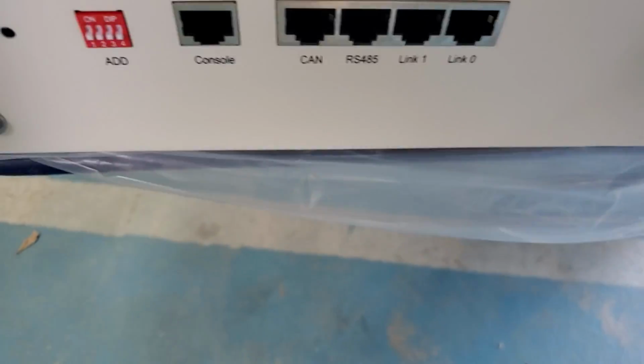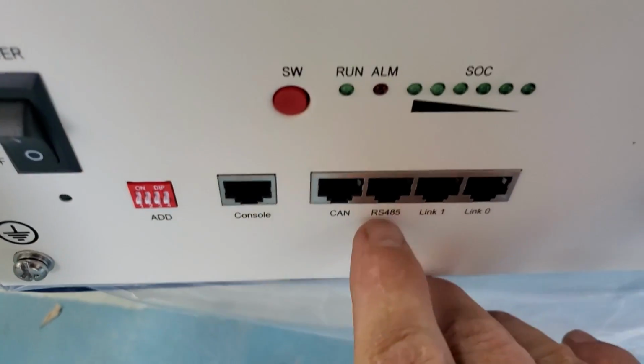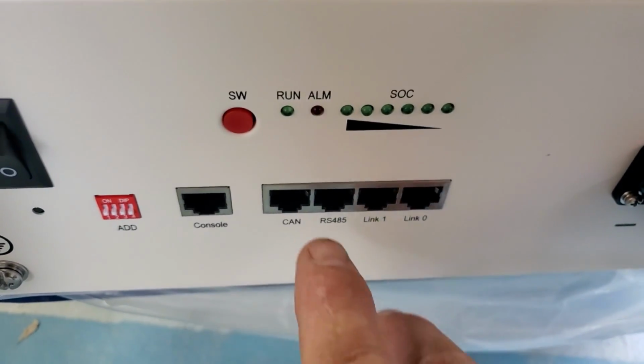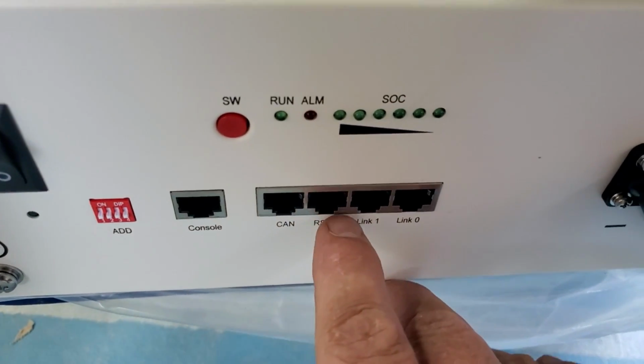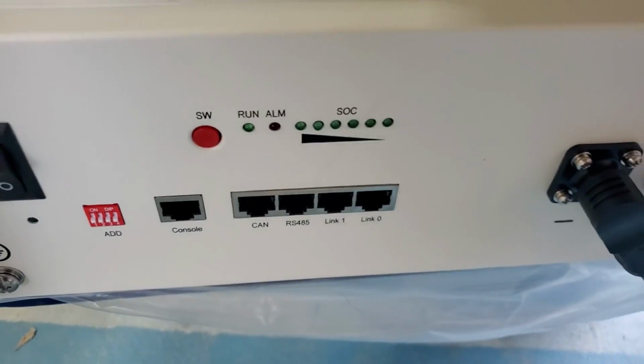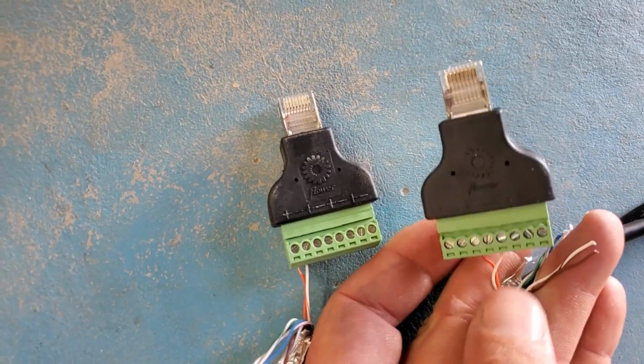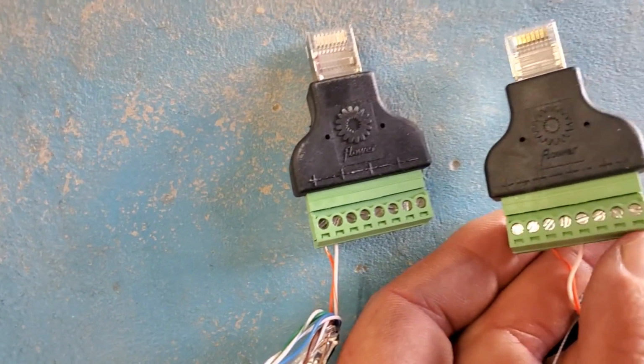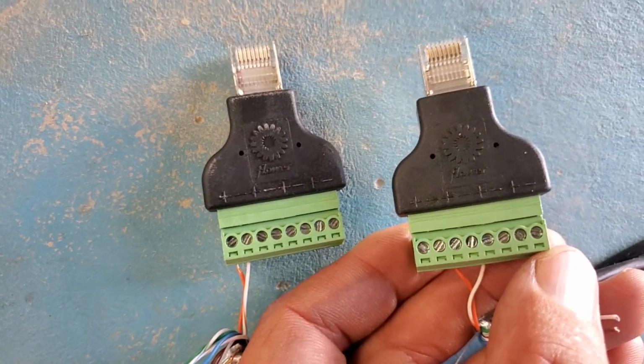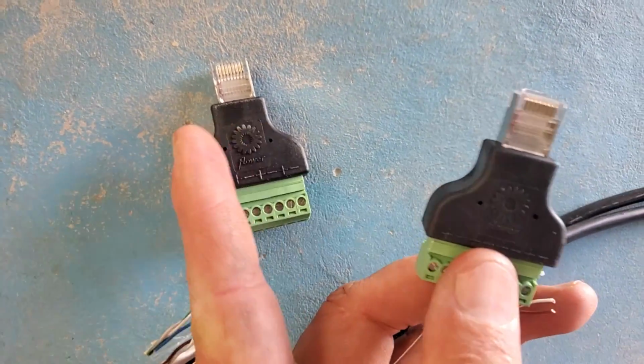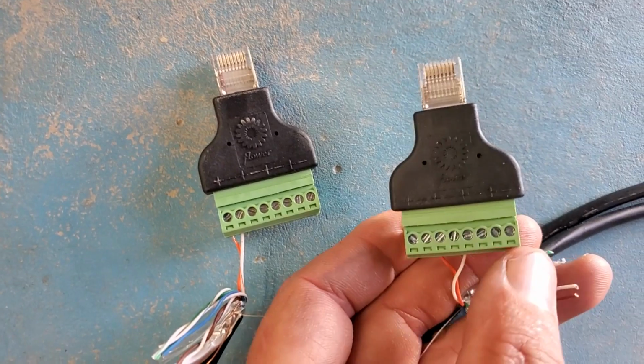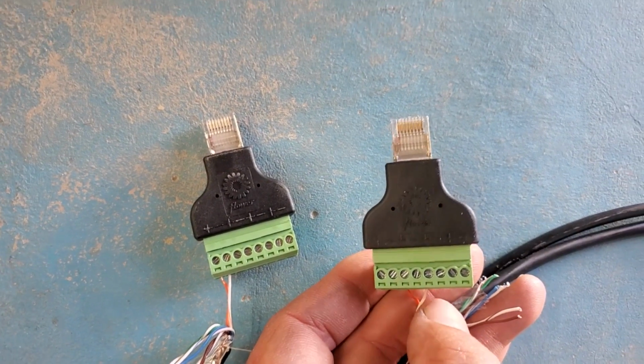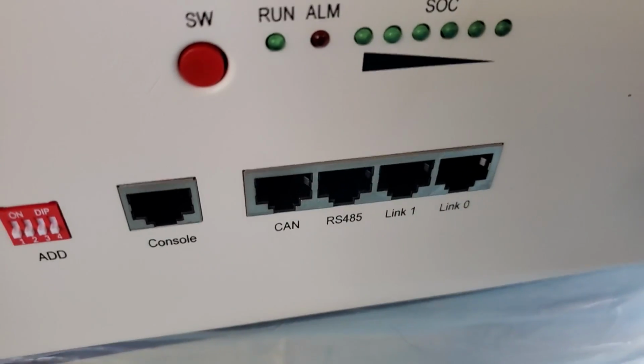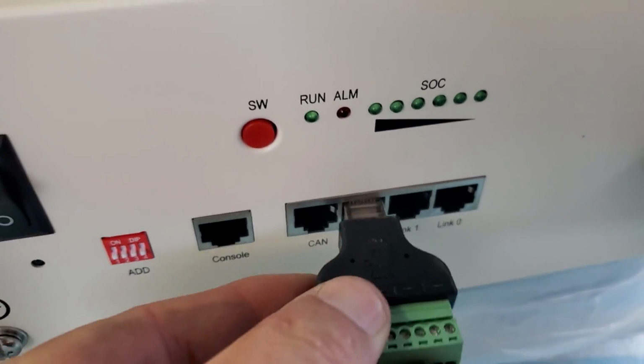We're going to use the RS485 port. This is a new battery, and the ports look a bit different from the older battery, and the pinouts are different as well. Here's a cable we made up: pins 1 and 2. Pin 1 from the battery goes to pin 3 on the inverter, and pin 2 from the battery goes to pin 5 on the inverter. We plug that into the RS485 port.